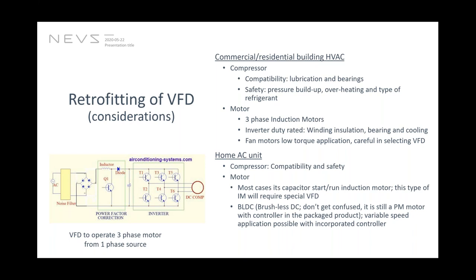Another important thing to be considered is with the fan motor, it's a low torque application, so we must be careful to select the appropriate size of VFD. It might be that you might be using an oversized VFD for a very small torque application or very small motor. You might be selecting a very big VFD, but this is the design consideration, or problem, that quite a lot of do-it-yourself groups have faced.